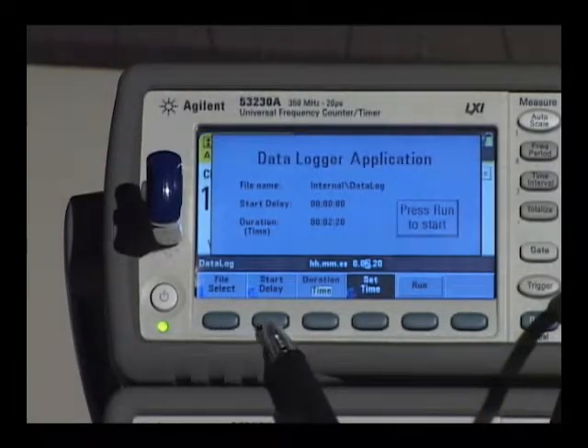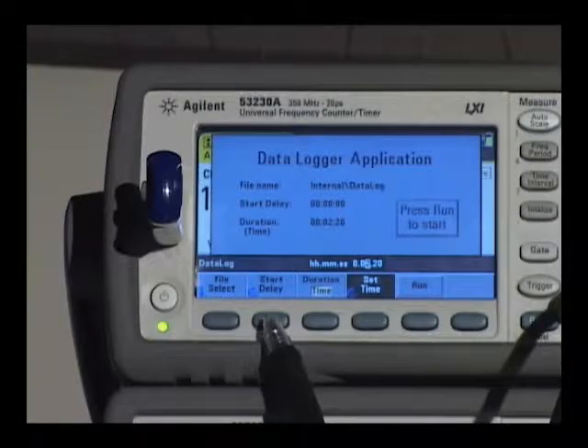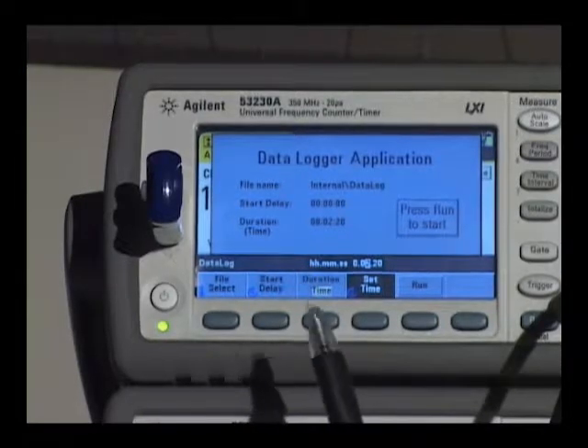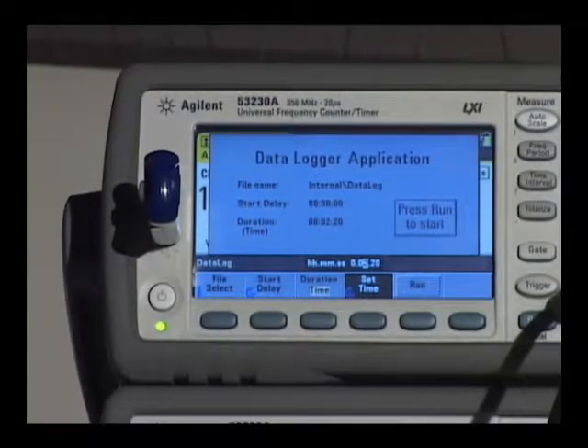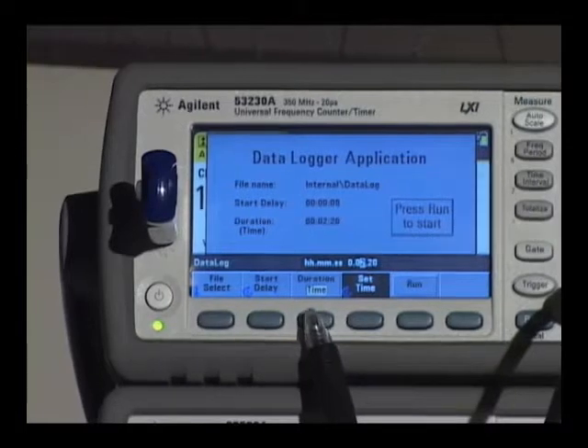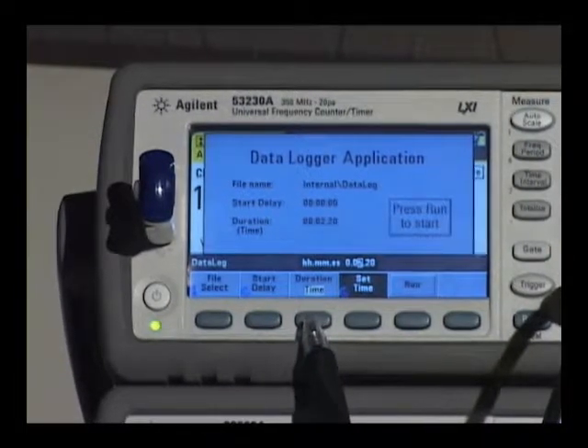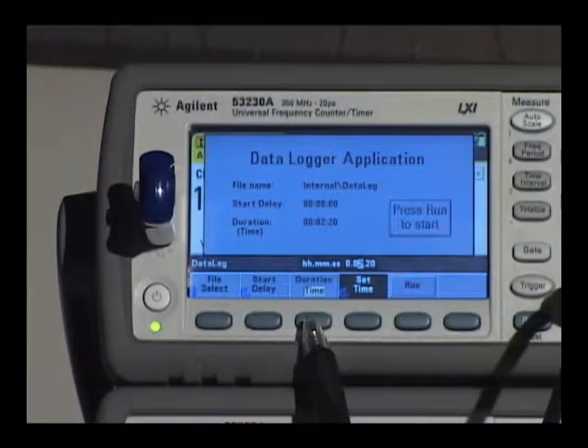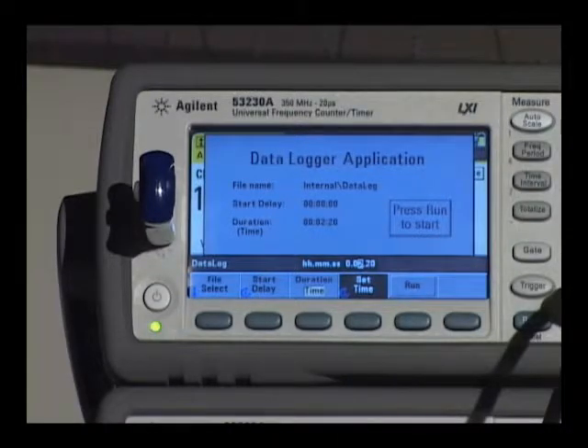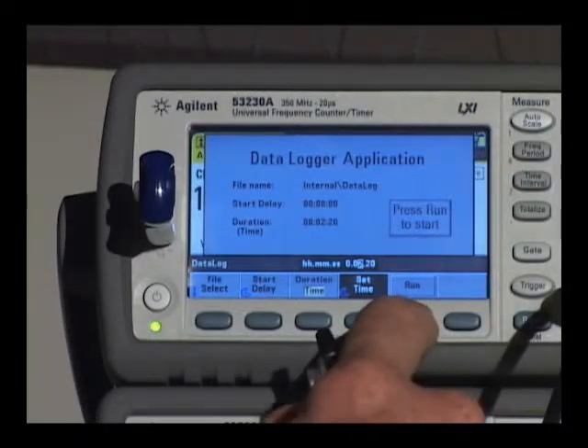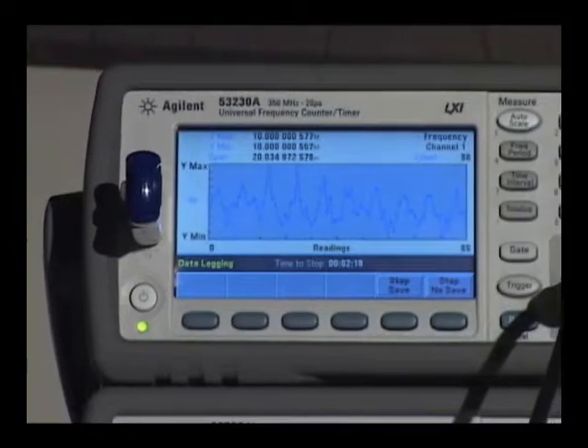The next process is setting up your start delay, which allows you to have a warm-up time before you're actually taking measurements. Then you can pick a duration of time or number of readings — up to 99 hours or 1 million readings — then press the run key and the data logging begins.